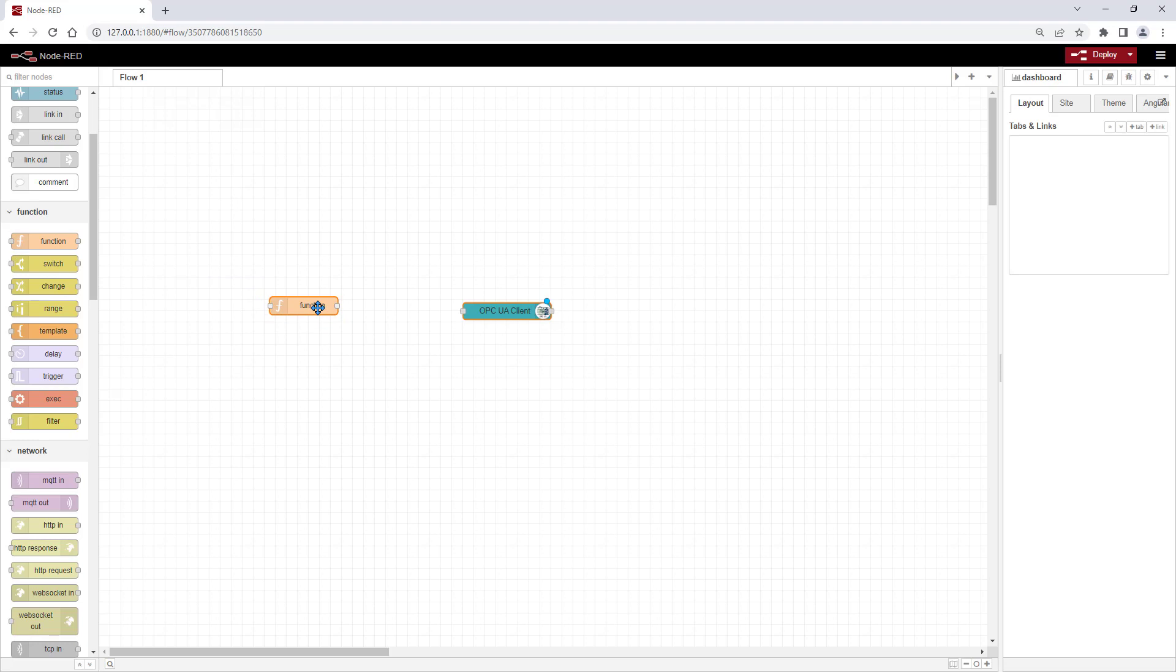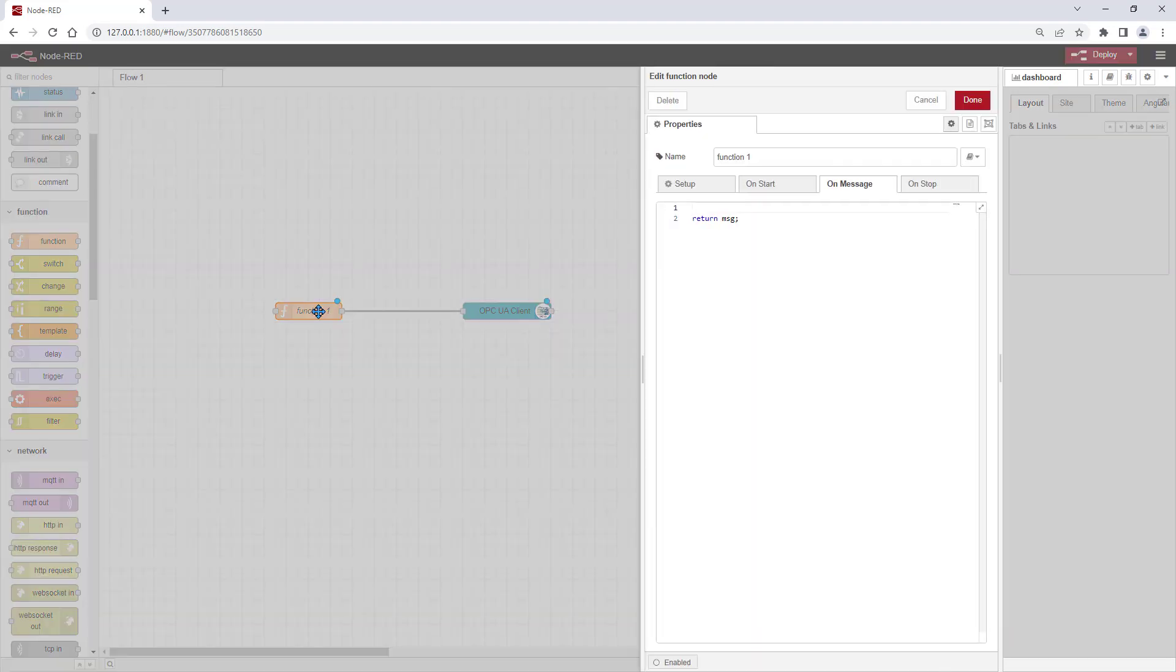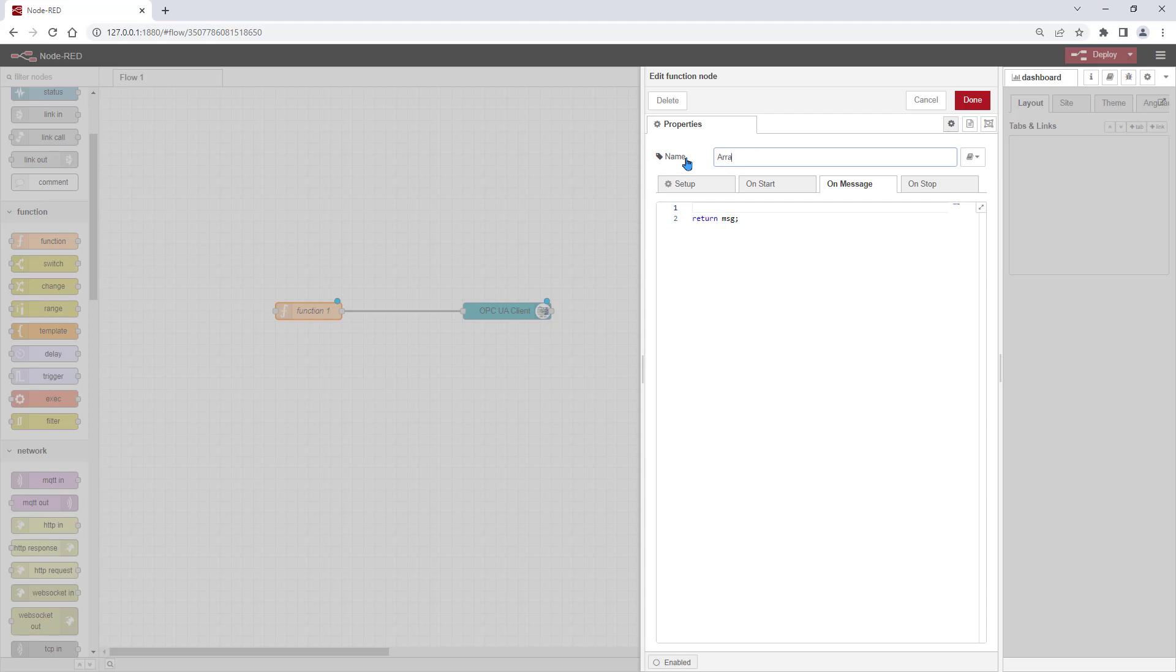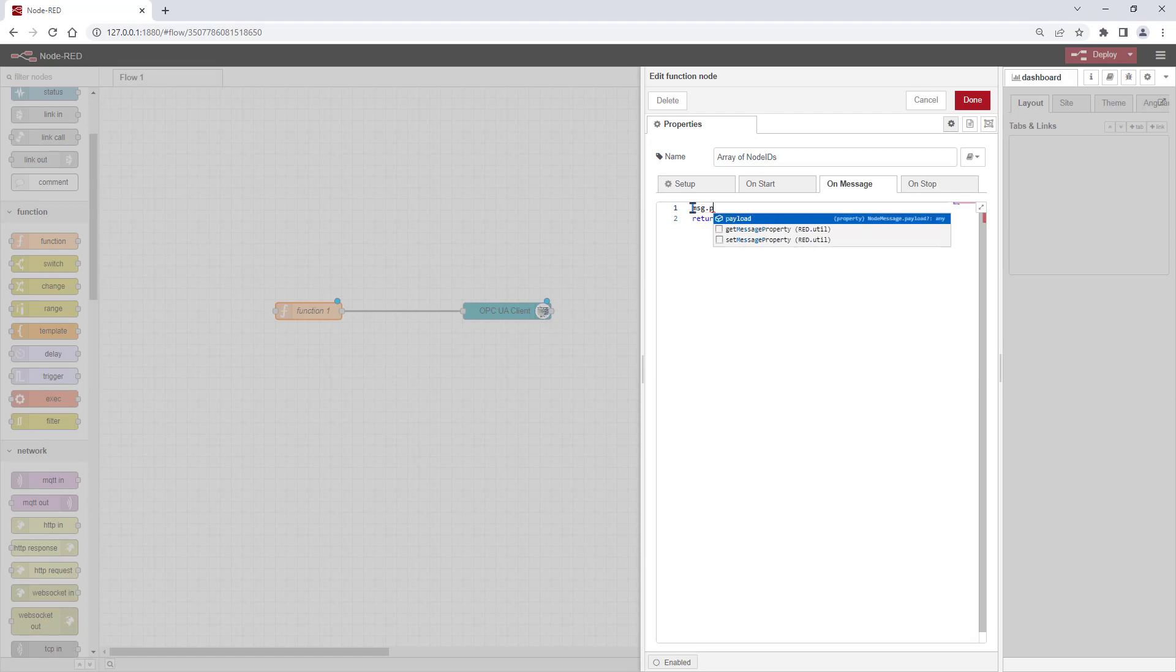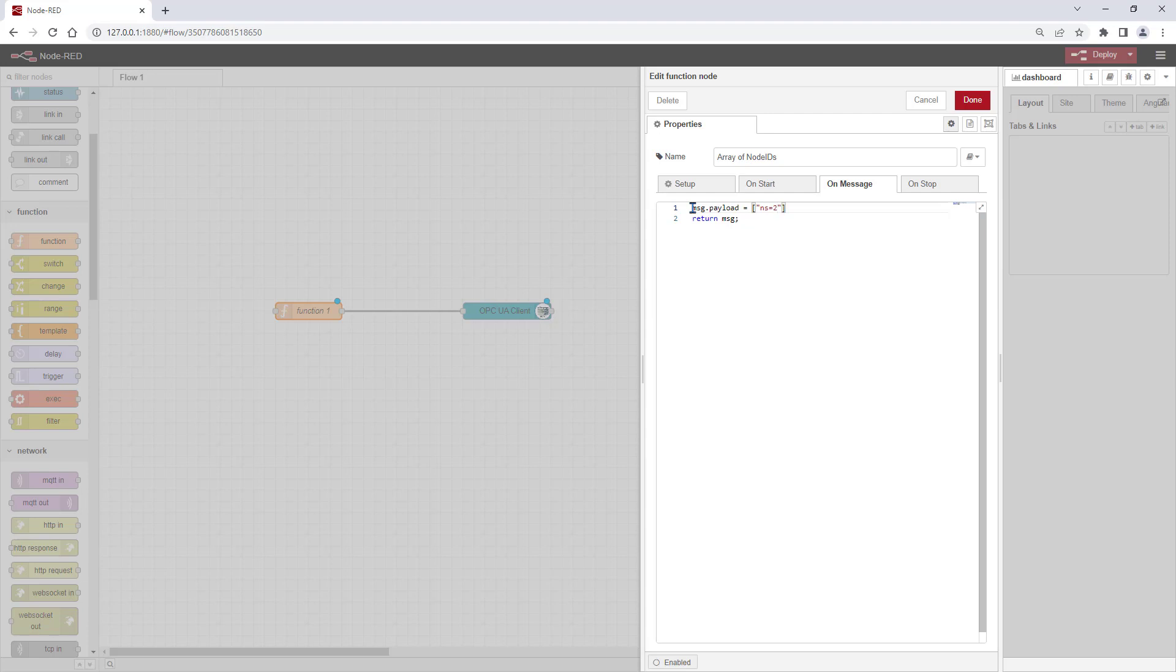With the function node, we define multiple tags which we want to read from the OPC UA server. For this we assign a list of node IDs to the message payload. This gets defined by the namespace, by the node ID itself and the data type.